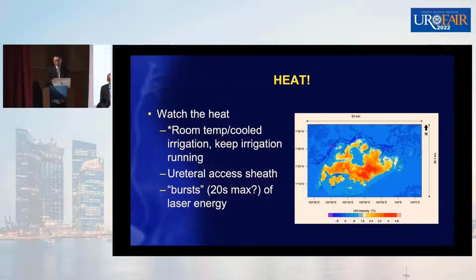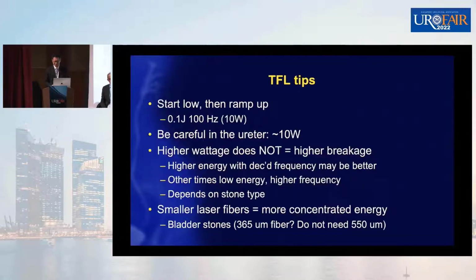I don't know what the proper amount of time is, but I sort of say maybe 20 seconds max, come off for 5 seconds to let it cool down, and then go again. It also lets you determine what the size of the fragments are, particularly if you're pop dusting. You want to see if there's any large fragments left in. So start low, ramp up.